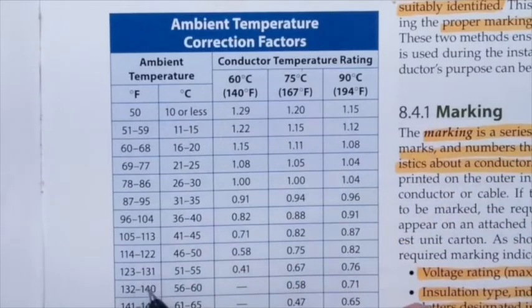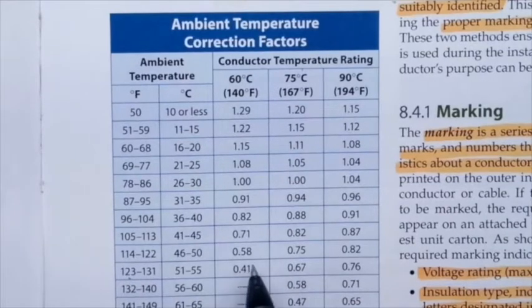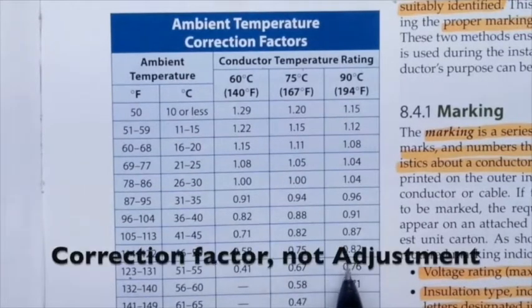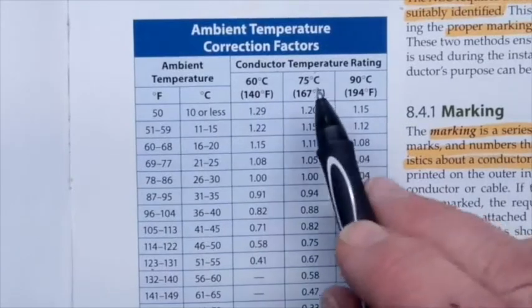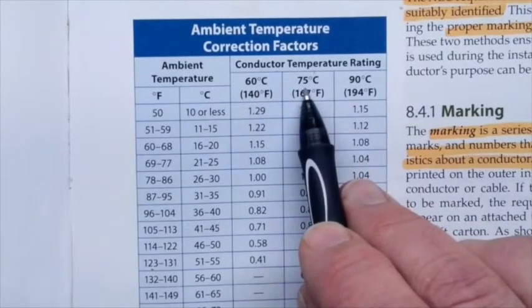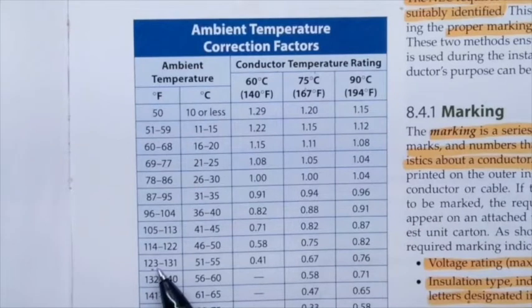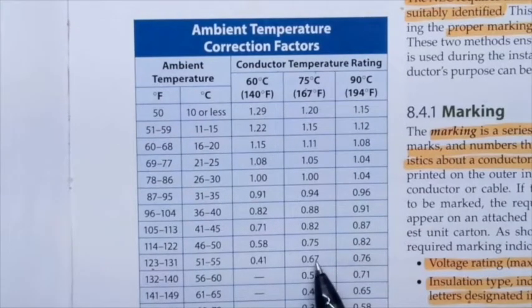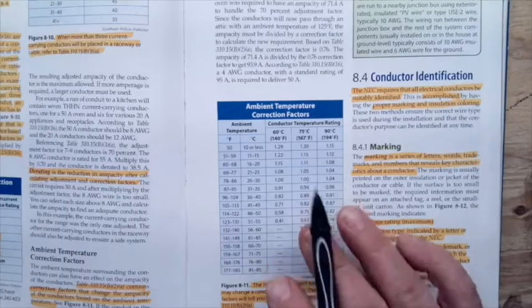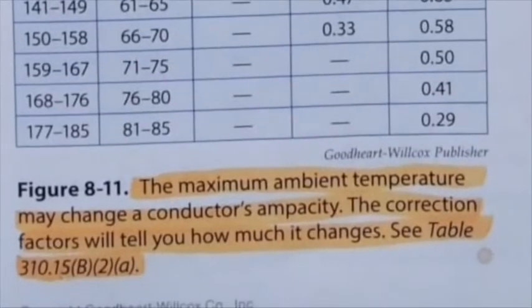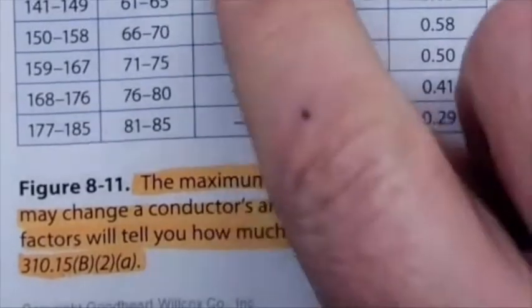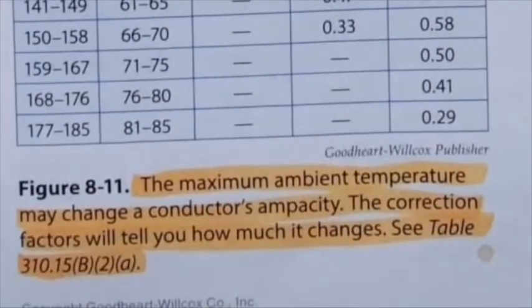So if the ambient temperature is 130°F — which falls between 123 and 131 — I come across the 90°C column and get a correction factor of 0.76. For THWN at 130°F, I'd use the 75°C column and get 0.67. This ambient temperature correction factor chart is found in NEC Table 310.15(B)(2)(a) — it's important to know where to find this in the code book.